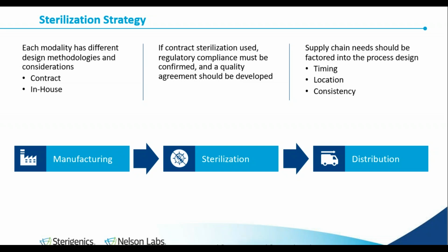and project or product managers that are guiding the development of the product, through to the manufacturing engineers that are going to develop the manufacturing process, to the operations folks that actually have to execute that manufacturing process, and the quality engineers who will be checking the manufacturing process. All of these folks are not directly involved in sterilization, but it's critical they understand the sterility assurance impact they have. So one of the tools that I used to like to use, and I was blessed to be taught this from one of the companies I worked for, was the development of a sterilization strategy.